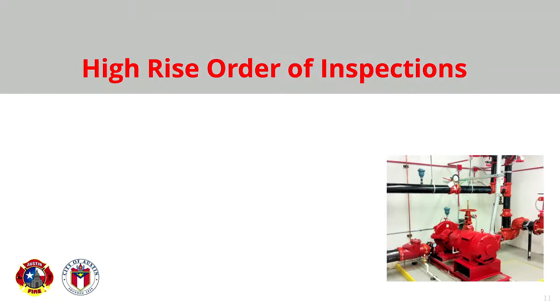So once the fire pump acceptance test has been scheduled and we show up, you're going to have your pump rep there. Again, this is going to be requested by your sprinkler company. Everything so far, other than the hazmat inspection, will have been requested by the sprinkler company. The hazmat inspection is going to be requested by the general contractor or the electrical engineer. Is that right? Yeah. I'm not involved with that one, so I'm not sure who actually does that one. Scott said you're right. Yeah, okay, good deal.